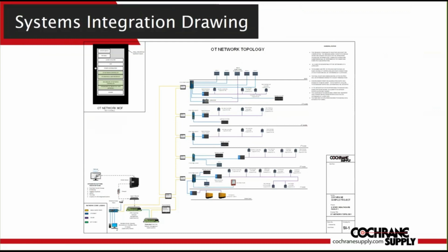I see what systems or technologies are actually being integrated into the overall system. I see that they want a separate OT network. I see that that network solution is using actual fiber to connect all the edge switches together. I see how many ports each edge switch has at each floor. I'm showing gateway devices.